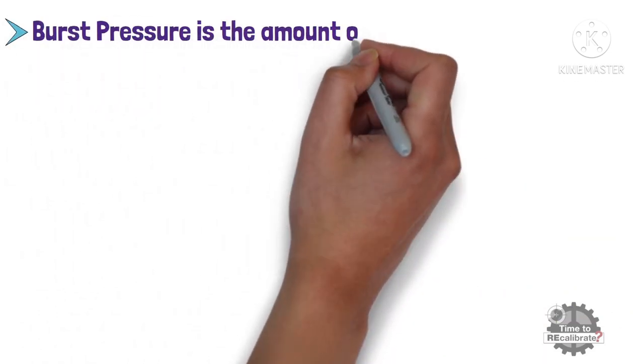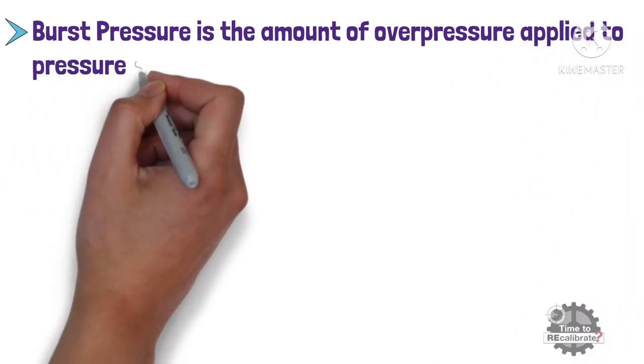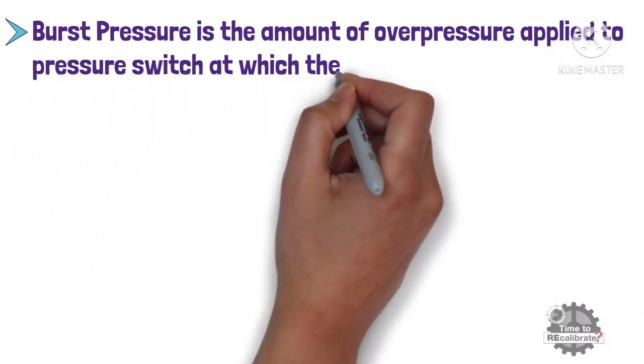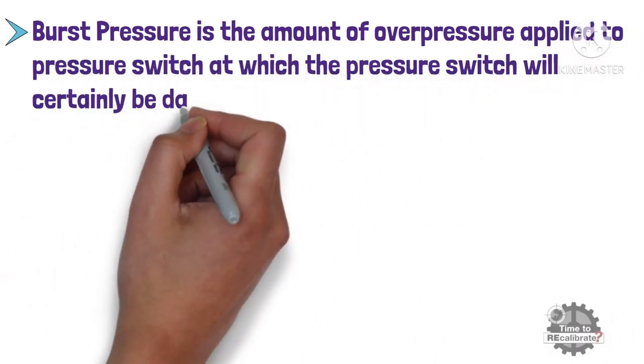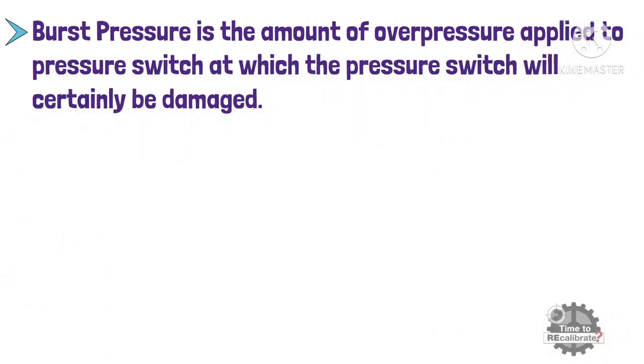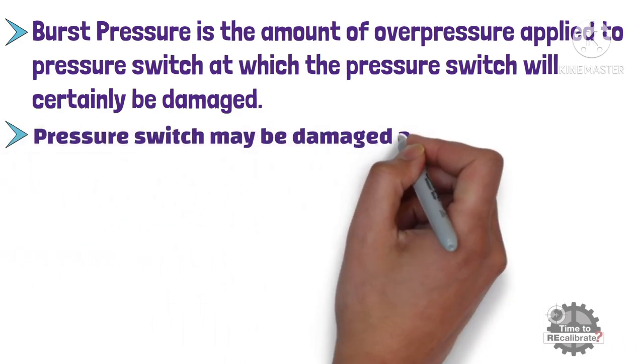Burst pressure is the amount of overpressure applied to a pressure switch at which the switch will certainly be damaged. A pressure switch may be damaged at any point between the proof pressure and burst pressure.